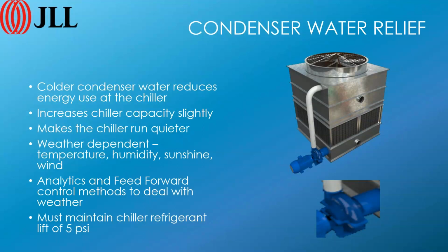Right. But if you set the PID control for that pump at 28 degrees, what's going to happen is that as the condenser water temperature goes up, the pump's going to start pumping harder and harder, and as it gets warmer outside, naturally the temperature spread's going to get higher, and the pump's just going to try to control the 28 degrees and won't be able to. It'll just keep going up till it gets to 100%, right? Right, which is fine. Yeah, that's fine. Okay, good.